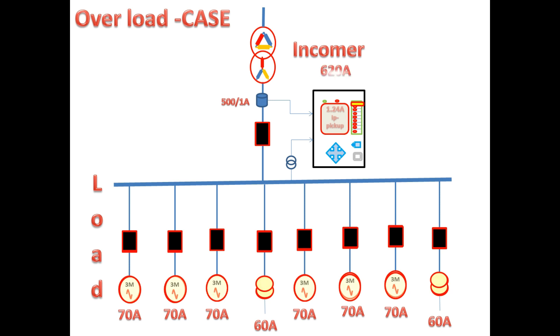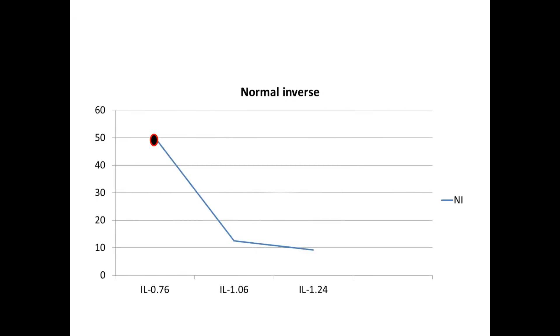In case 3, here also all outgoing feeders are having overload but the actual current is quite higher than the previous case. We have 1.24 Amps in the secondary. When we substitute in the formula we got trip time 9.26 seconds. It is clear that when the fault current increases, the tripping time is getting reduced in IDMT.